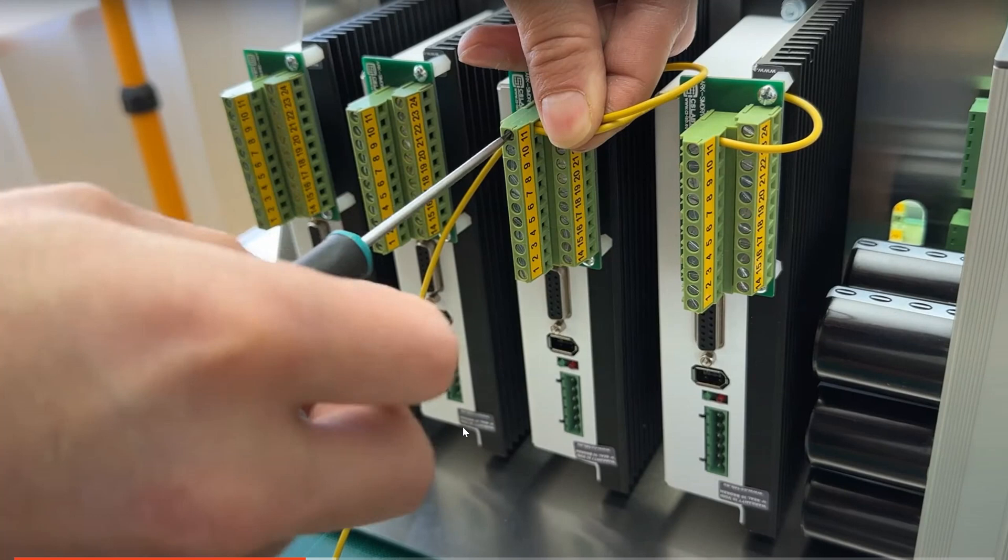Okay guys, just to clarify what we're looking at here, because this is going to interest many of you. These are servo drives. I know many guys out there go crazy about 'I want to buy servo drives, they're so much better than stepper.' Here's what's interesting about this video and is ironic: this is the manufacturer of these drives sponsoring this video. And I'll state that again, this is the manufacturer doing a video of their own drives and they are inserting two leads inside a single point terminal block.